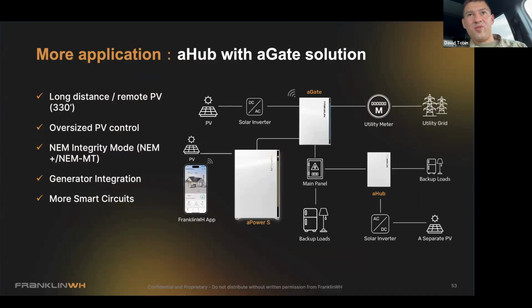If you're just using the aHub for that AC coupled solar, we also have the ability to do RS485, which is two small wires -- make sure it's like number 16 -- and you run that if you already have conduit in place, or you could run another small conduit and run those two wires out to the barn. That way we have the ability to monitor, essentially measure the current, and also relay it if you're ever off grid and we need to control that AC coupled solar.